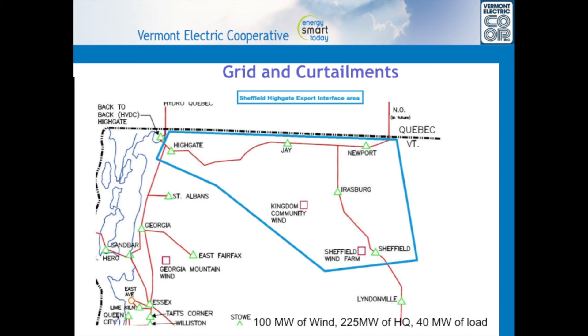What we did to fix the problem was put a big flywheel on this. Between the wind generator and the grid, we have this massive flywheel. We introduce inertia, so the output of the wind goes into the flywheel and spins it. If you ever go up to Jay Vermont and Jay Peak, you can send me a note and I'll tell you where our sub is. You can see this huge building that looks like a barn, there's just a big flywheel in there. One end is an electric motor, the other end is a generator, and in the middle is this big flywheel.